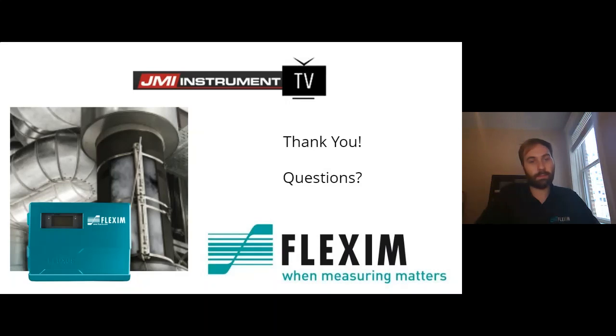So whichever phase is prevalent would be the way you'd want to measure. So if it's liquid with some aeration, or if it's gas with a little bit of liquid, you'd want to measure gas in that case. If it's liquid with a little bit of aeration, you want to measure liquid. Transit time can tolerate, depending on how much signal you have to work with, about 5 to 10% aeration. So if you're talking about a gas or a liquid that's at its boiling point, you want to be sure where you're mounting the transducers. You want to try to find a place that doesn't have pressure drops, or try to measure right behind a pressure drop, say a valve or something like that. Because if you drop pressure, most likely you're going to start gassing.